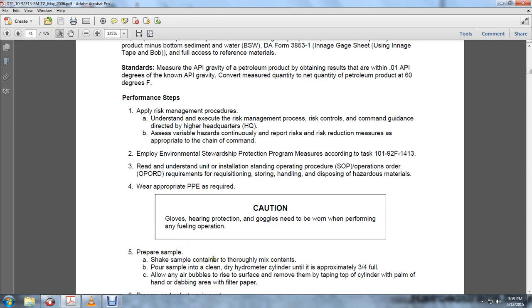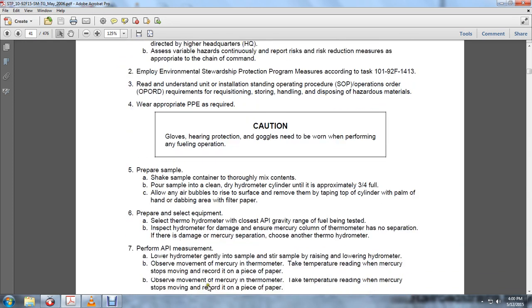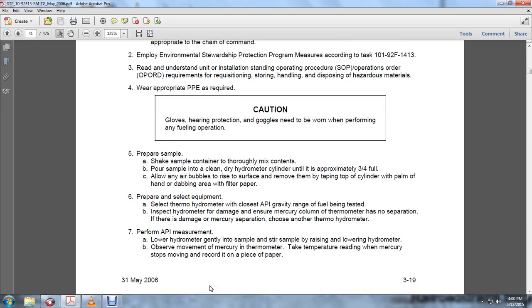Prepare the sample. Shake the sample container, fully mixing the contents. Pour the sample into the clean hydrometer cylinder, approximately three quarters full. Allow any bubbles to rise to the surface, or remove them by touching the top of the cylinder with a piece of filter paper. Prepare and select equipment. Select the hydrometer with the closest API gravity range to the fuel being tested. Inspect the hydrometer for damage, ensuring the mercury column of the hydrothermometer has no separation. If there is mercury separation, change to another hydrometer.